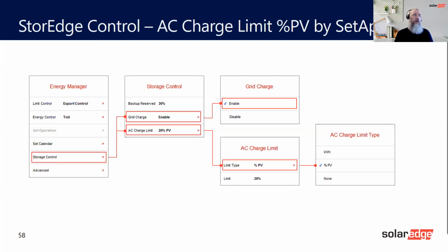Again, you've got a different one here. We've got a backup reserve on there of 30%. That's the other thing that you need to bear in mind when you do have the backup device, which is coming: to make sure how much battery you want it to discharge to. So if you have a 24 kilowatt one like the BYD, you could set the discharge maximum to 50%. So you'll always have 12 kilowatts of battery there.